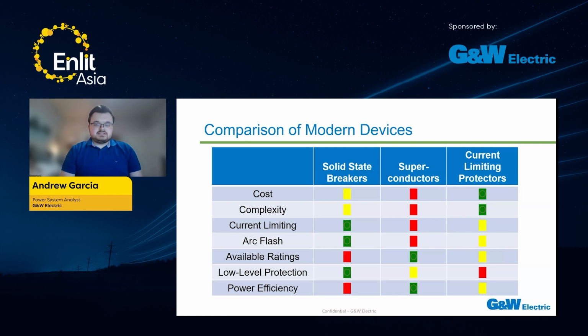In terms of available ratings, superconductors, of course, are going to be the best because, with infinite current density, you can apply them to basically any kind of rated system. Current limiting protectors come in second, as they can go up to very high ratings, up to 38 kV, with very high continuous and very high short circuit ratings. In last place come solid state breakers, because there are significant trade-offs in terms of size and efficiency as you increase the size of those breakers. Now, in terms of low-level fault protection, solid state breakers are the best. Superconductors come in second, because they'll still be adding that impedance to the system. Current limiting protectors come in last because they're not designed to mitigate low-level faults.